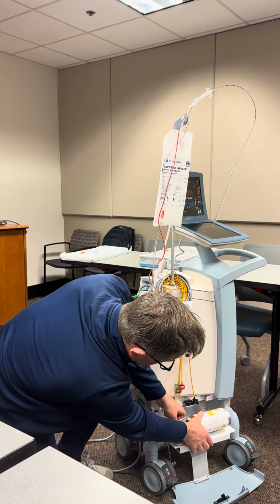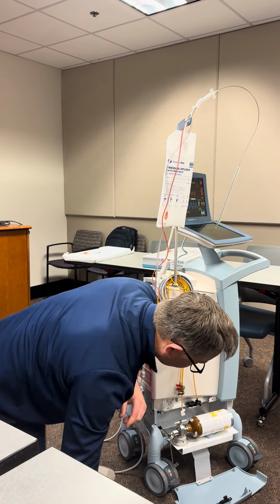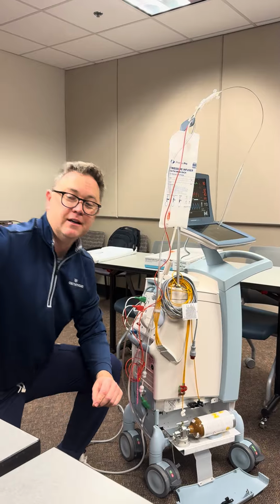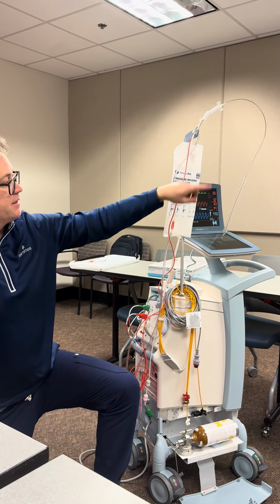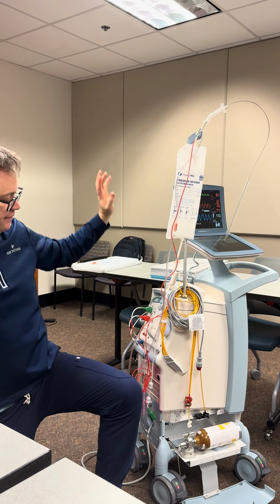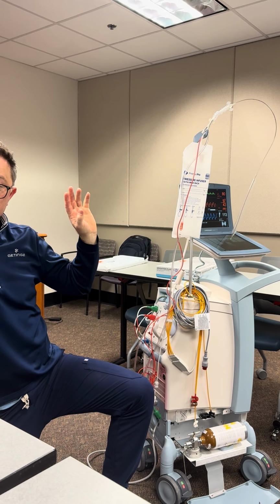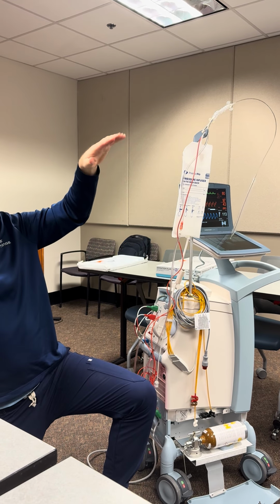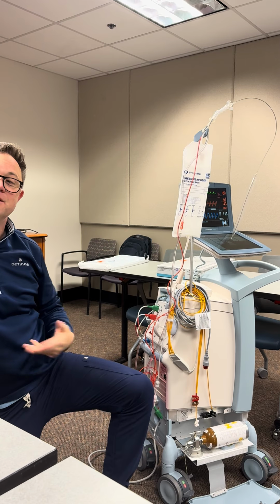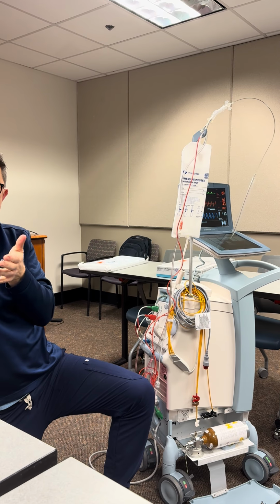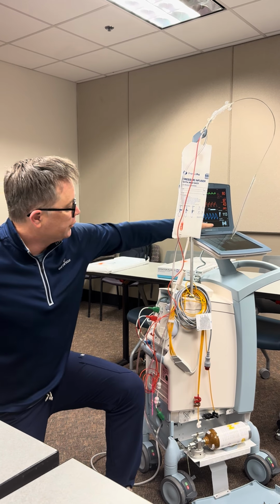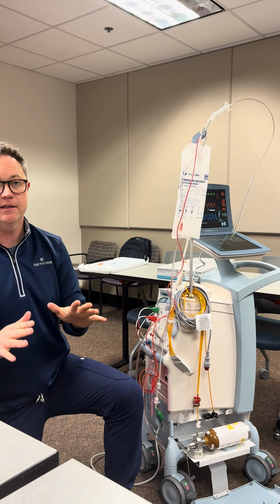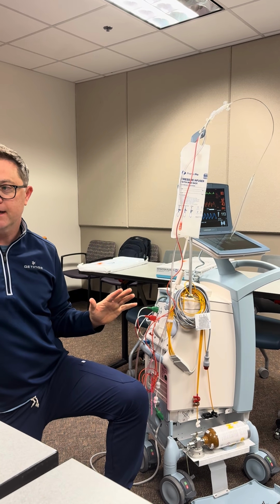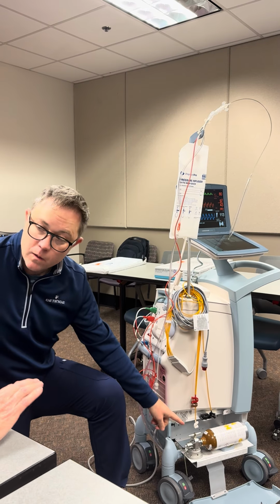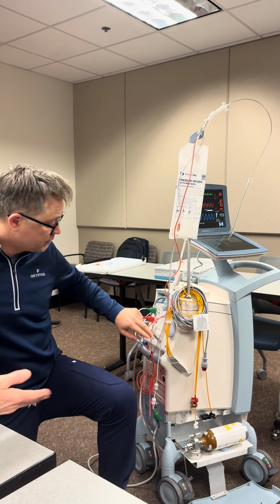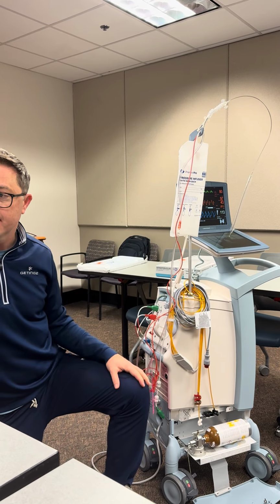And how much helium do you have in the machine when you take the tank off? It's what we call 24 autofills. So every 2 hours, this balloon catheter will flush the line and refill it. Like your helium birthday balloons, the next day helium dissipates. Before it dissipates, it flushes it. So you shouldn't dilly-dally too long with it. I guess the point is, when you get a low helium alarm, you don't have to change it. It's not like you're going to run out within an hour. You've got a couple days to figure it out. I'm just wondering when you have the tank disconnected, how long has it been? 24 autofills. Okay. Yep.